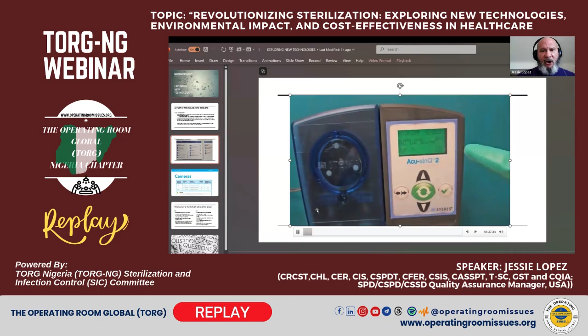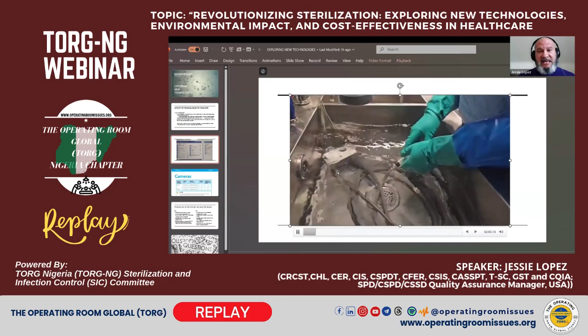Now, our second bay, we fill up with 10 gallons of water, and we use automated dosers to dose our chemicals into the detergent, into the water. And our detergents function between 90 and 120 degrees to be able to activate the enzymatic components of that detergent. Now, I don't know if you can see in the far end here, me dosing out my chemicals here. And now I'm going to transfer my device into the soaking bay. Now, the IFUs of this device requires that this single camera stays soaking in detergent for 30 minutes. 30 minutes of soak time.